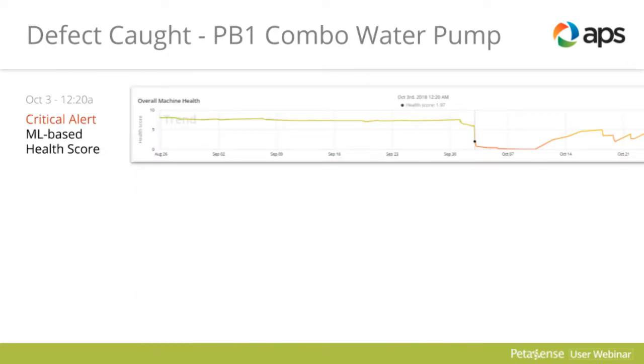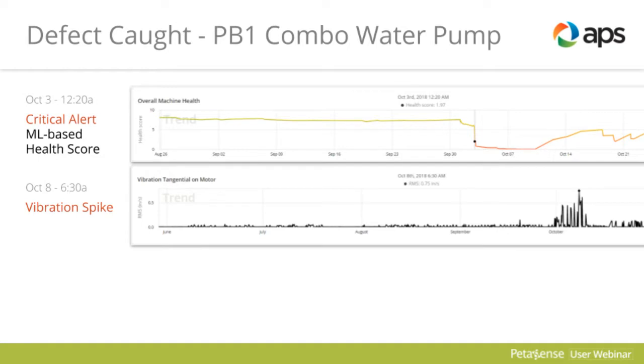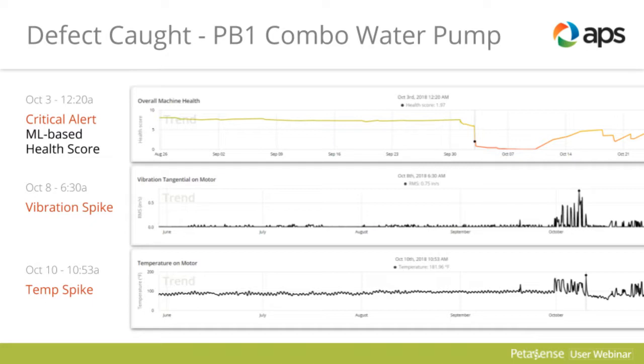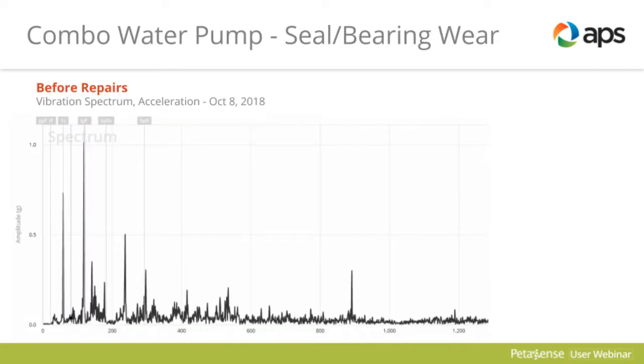Shortly after that, right around October 4th, you'll see that the machine health started taking a big drop. You can also see that there was a vibration spike. This is on the motor drive-end. About 3 or 4 days later, we started having a spike in the temperature. So I called the plant and asked them to go out and check the pump and motor and see what was going on. They said that the gearbox was starting to fill up with water. And this was the readings.